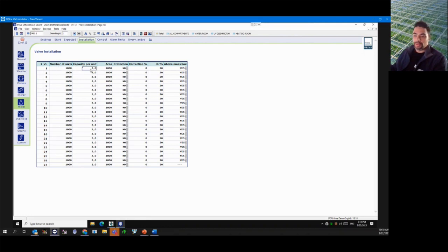So when this valve runs, you basically just multiply these. So it's 1,000 times 2, so that's 2,000 liters an hour, and 1,000 liters an hour is 1 cubic meter an hour. So we know that when this valve runs, our expected flow rate, our calculated flow rate, is going to be 2 cubic meters, right? So that's what the flow sensor should measure, 2 cubic meters.